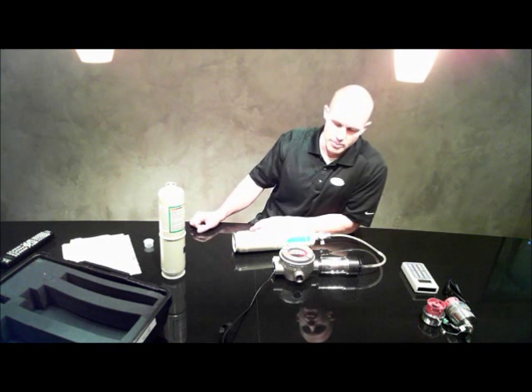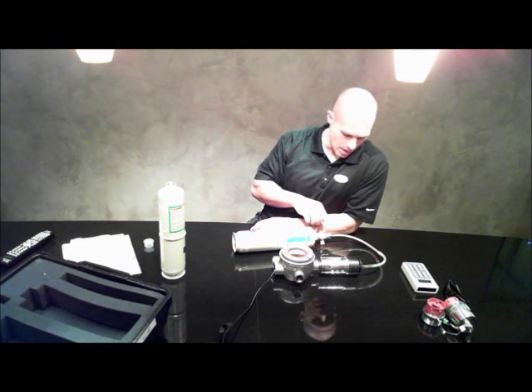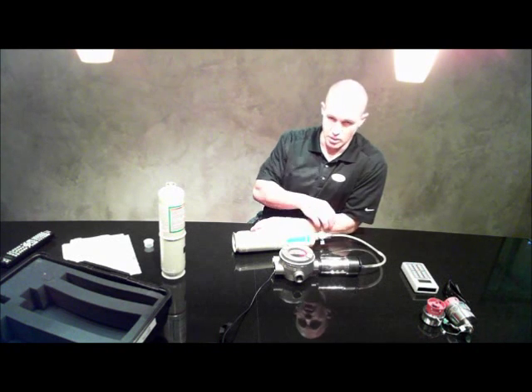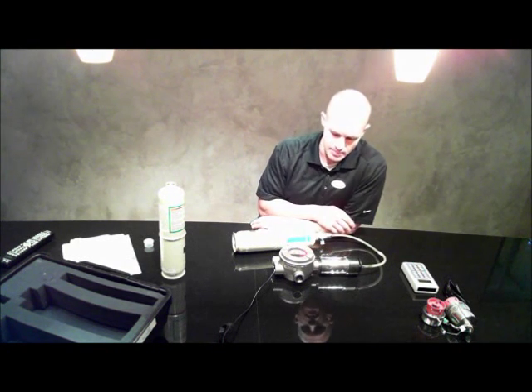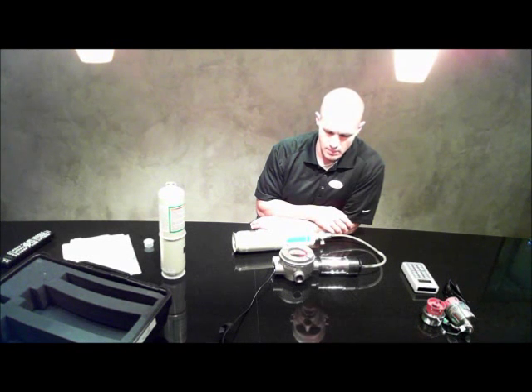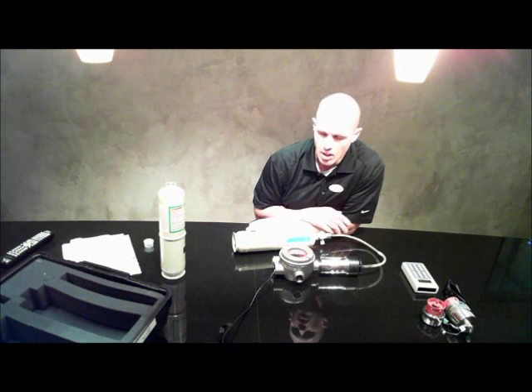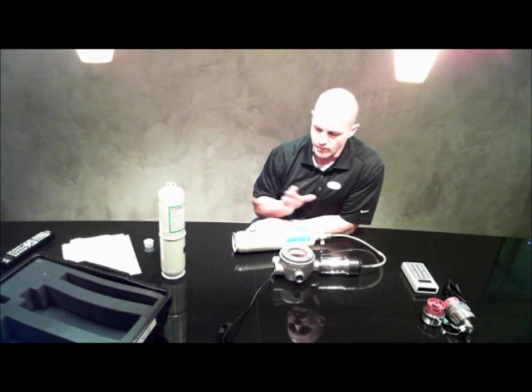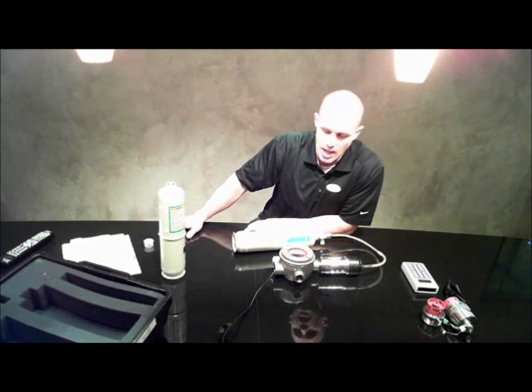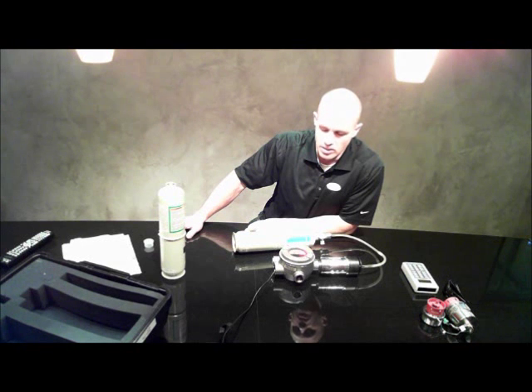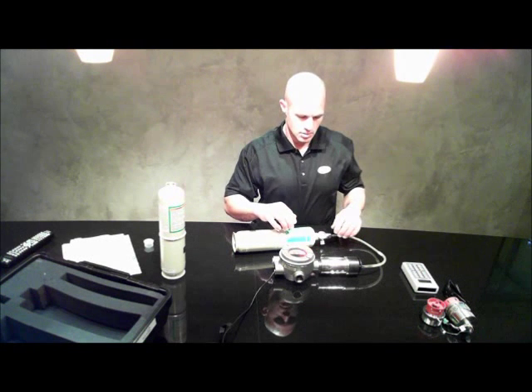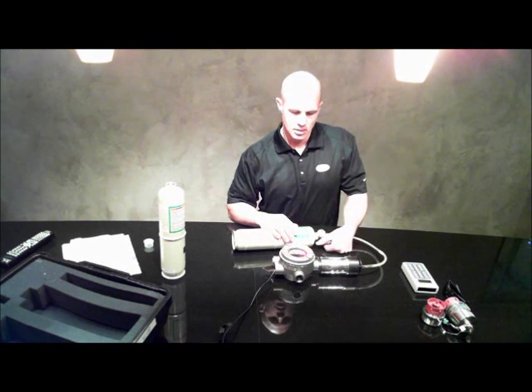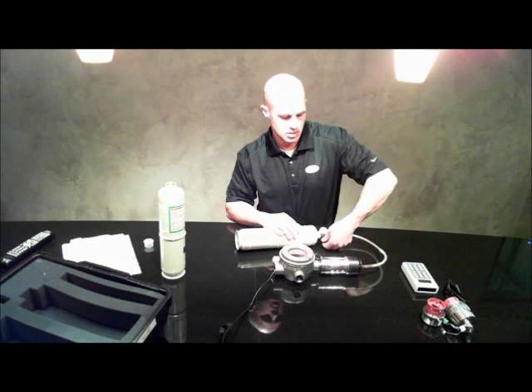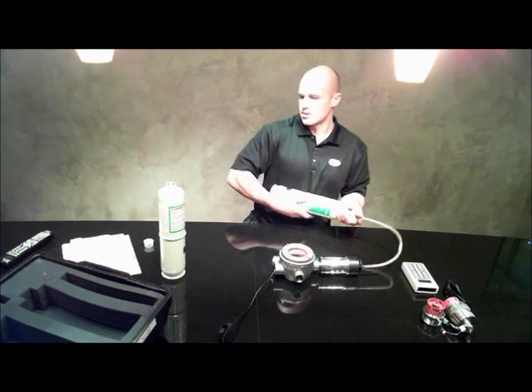For a minute there it showed 1% LEL, but that was because there was some methane gas in here that was being pushed into the sensor. So it's back down to 0. With these IR heads, technically you can get away with just doing 0, but I think it's a good idea to go through the full 0 and span calibration, just to make sure it's definitely picking up a reading. So it says end, so we'll take off our 0 gas.